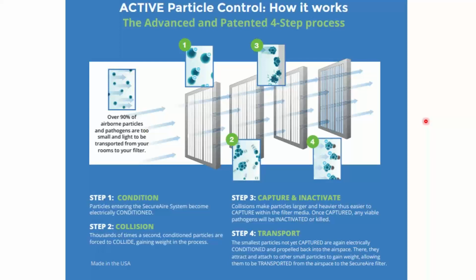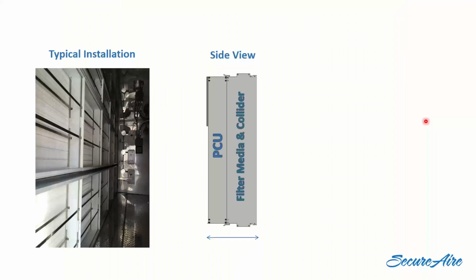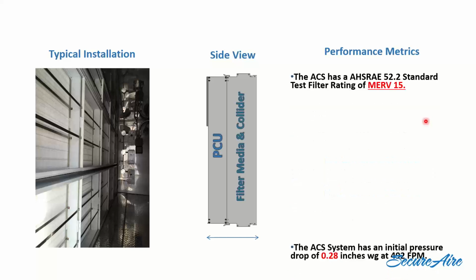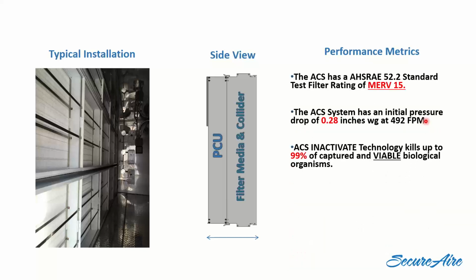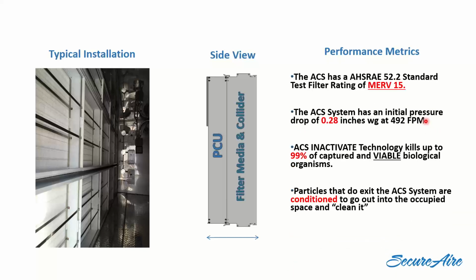So not only does this kind of filtration work at the air handling piece of equipment, but it also works on doing stuff to help you in the actual occupied space. That's what one looks like over there on the left-hand side when it's installed. You typically need a decent amount of space for this guy. It is fairly wide, not as wide as a HEPA system, but fairly wide, 9 inches in thickness.